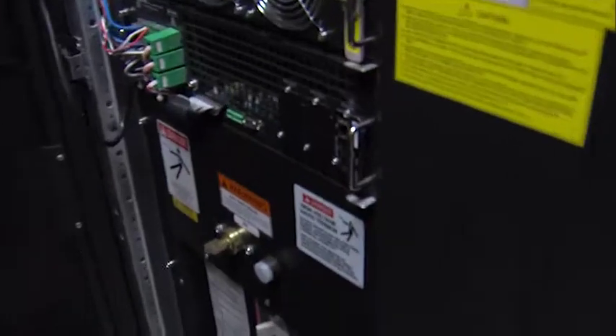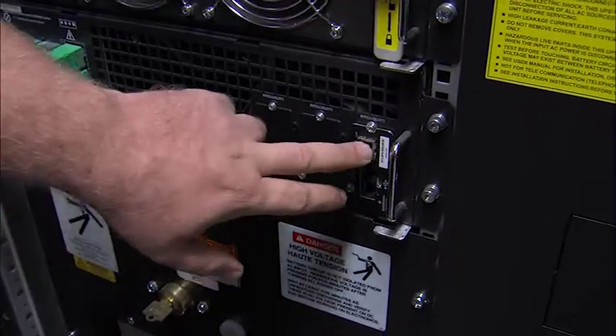But again, the SNMP card, which is right here. Once we have that programmed, we'll be able to plug into your network. These were supposed to have the SNMP, the Ethernet, and also the Modbus? Modbus. Yep. Remember? Yeah, this is a Unity card. So it has that ability. Modbus typically is a 4-pin connector, so they have RJ45 connector adapters for 4-pin. Because this is a Unity card, it can do Modbus, BACnet IP, and SNMP. We're going to need some instruction on how to hook all that up, because we got the wiring in here. You do have it? Yeah. Okay.